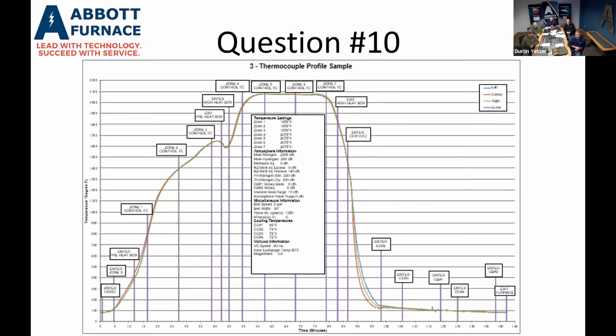The other temperature deviation they're asking about is the temperature deviation in the zone. That is the difference between the process value temperature and your set point value temperature. So if I have a zone that's set at 2075, typically the deviation alarms are set about 20 degrees F from set point, plus or minus. If I go below 2075 by 20 degrees, typically the horn fires. The horn will sound, giving you an alarm that says there is a deviation in a certain zone.